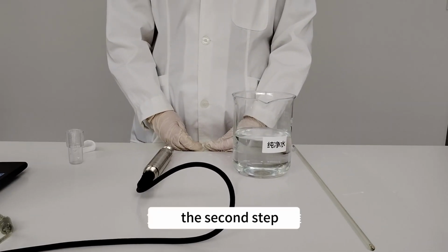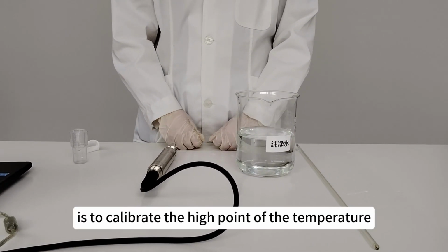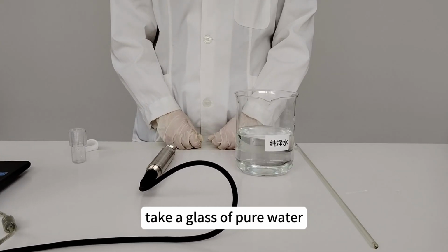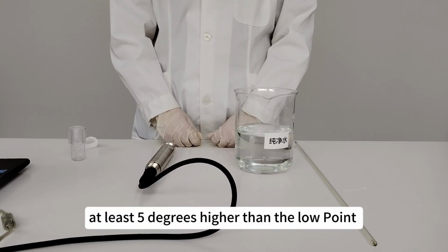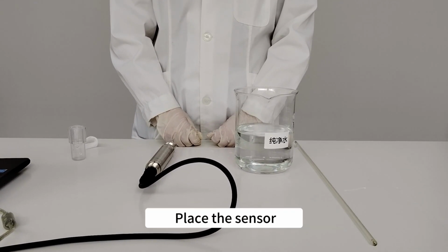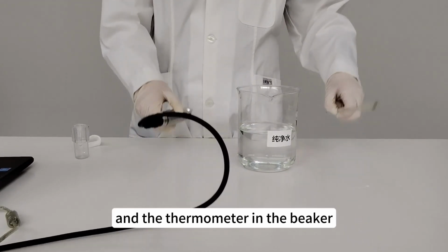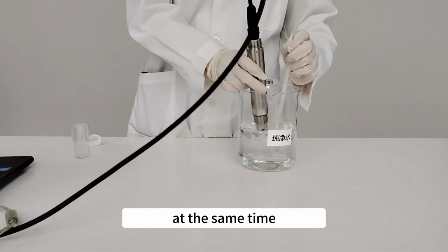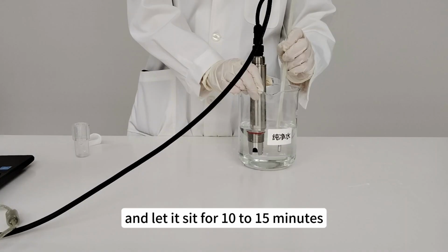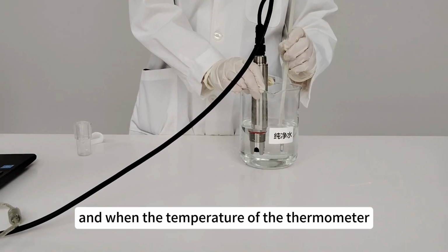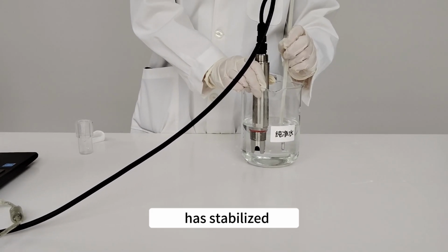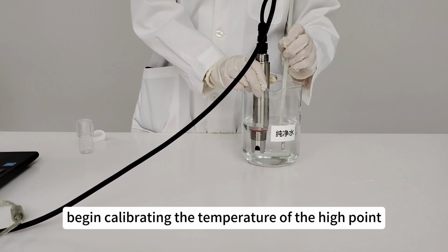The second step is to calibrate the high point of the temperature. Take a glass of pure water at a temperature at least 5 degrees higher than the low point. Place the sensor and the thermometer in the beaker at the same time and let it sit for 10 to 15 minutes, and when the temperature of the thermometer has stabilized, begin calibrating the temperature of the high point.